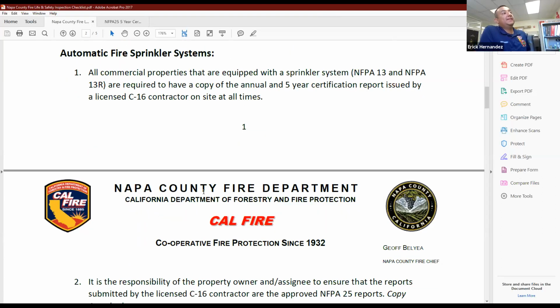So let's talk about maintenance. If you have a sprinkler system in a commercial setting, there are 3 types of sprinkler systems: NFPA 13, 13R, and 13D. A 13D is domestic, so those are installed for single-family dwellings and duplexes. A 13R is residential. You'll typically find those in B&Bs, hotels, motels. And NFPA 13 is commercial, so wineries, tasting rooms, restaurants, industrial. That's the difference between all 3.